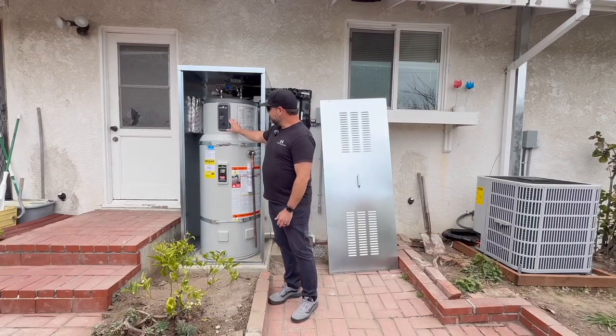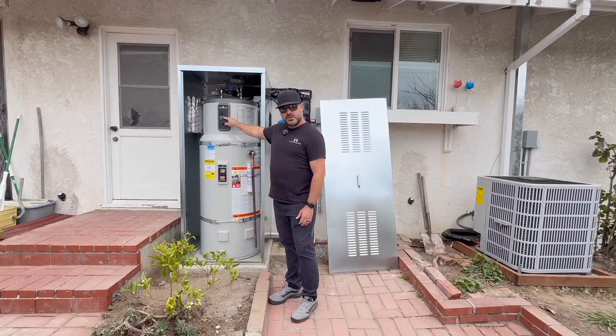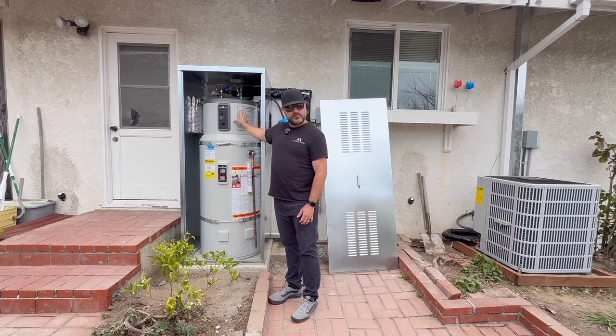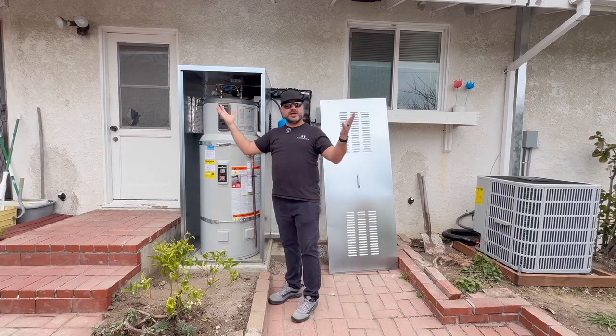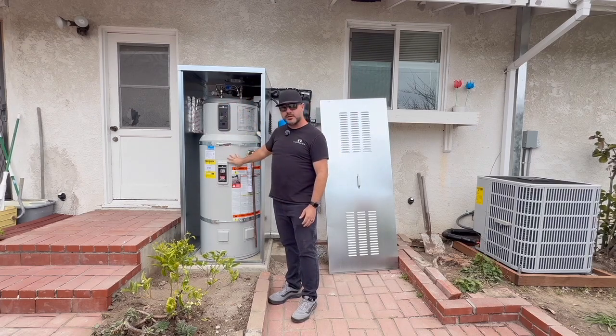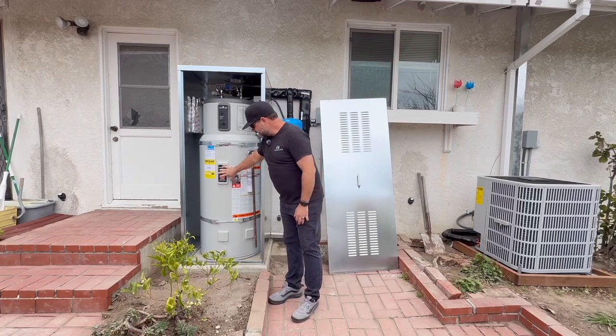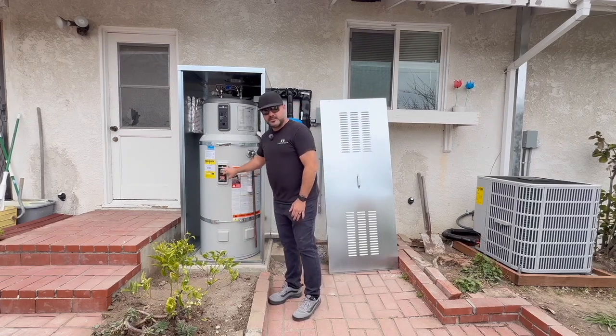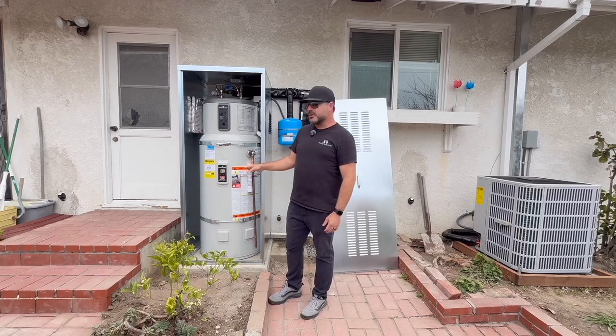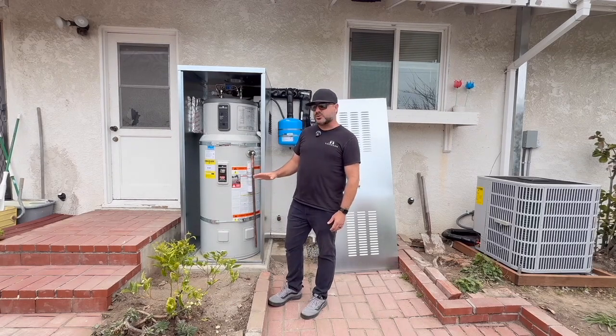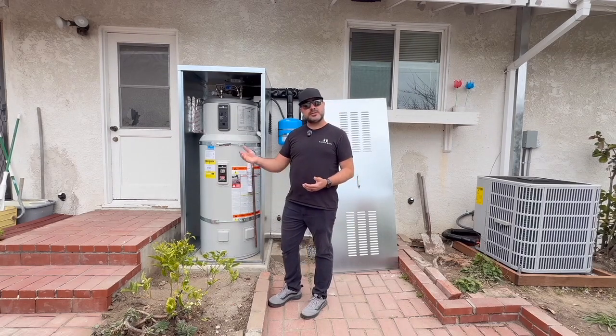We currently have this unit set on hybrid plus mode, which is using the heat pump, the refrigerant, to absorb heat in the air outside and transfer that heat into the water. But it's also using these electric resistive heating elements to heat the water faster. We just finished this install, so we're trying to get the customer hot water as quickly as possible.